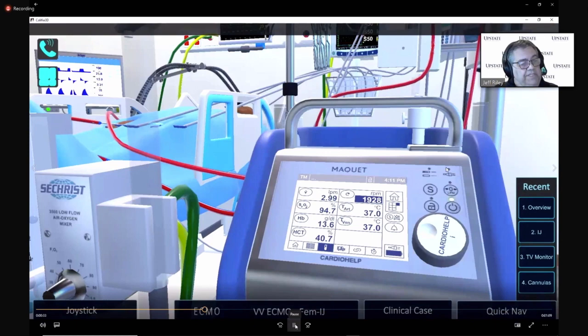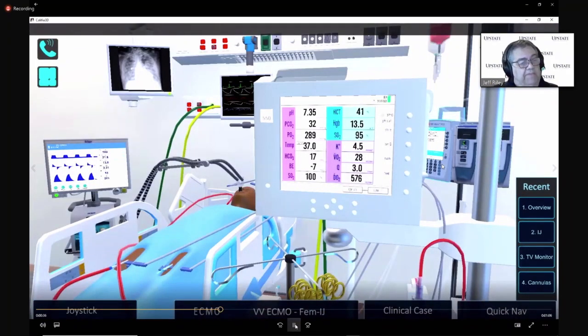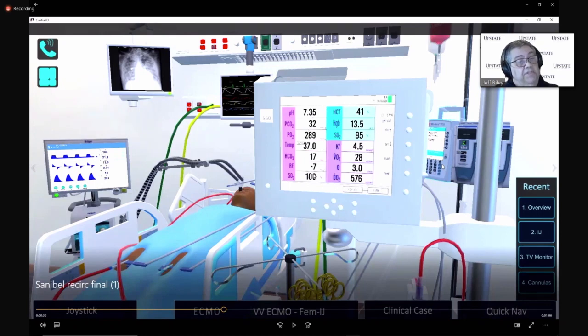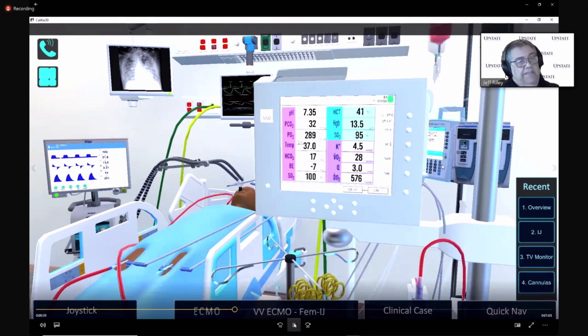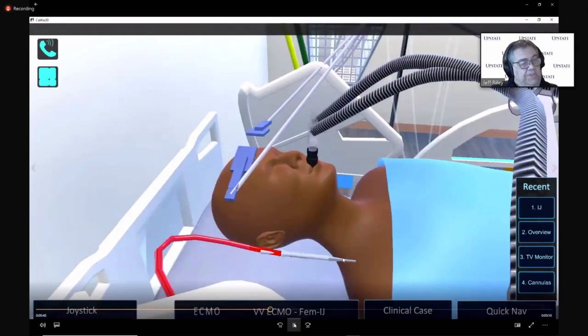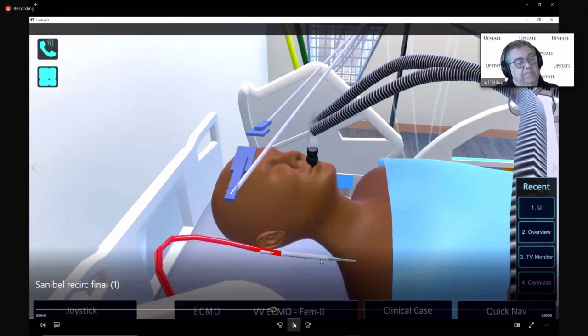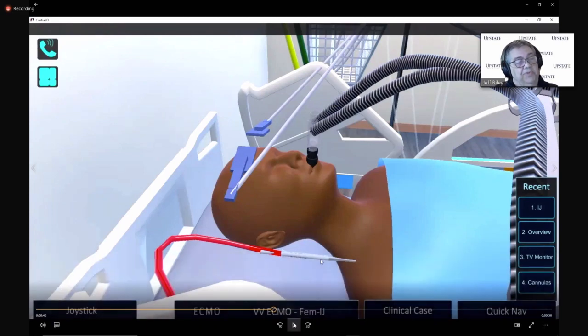We can go around and check some other things. In the room, we had the capability to hook a CDI device to the circuit. And it, of course, reads the arterial blood in the circuit, going to the patient's right internal jugular. And you can see that this is pretty acceptable. There's a high DO2, a low oxygen transfer rate in the circuit because the venous sat is elevated. So the fact that there's plenty of volume, a -4 pressure venous would suggest to us that perhaps the cannula tips are too close together.